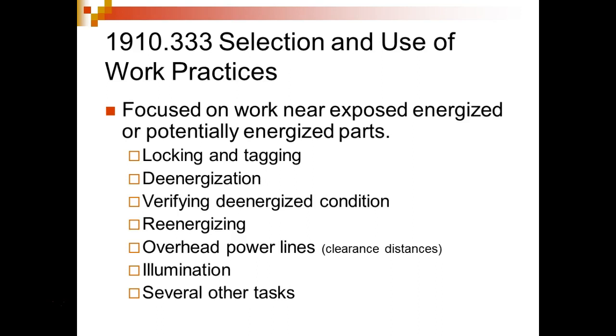We're required, I think, in this class for you to have your voltmeter, right? Anytime you lock out, or we use gauges. If it's pneumatics or hydraulics, we use pressure gauges. This is why just about every pneumatic and hydraulic lockout has a pressure gauge on it. Unfortunately, they don't put voltage meters on there because they depend on you to have one.